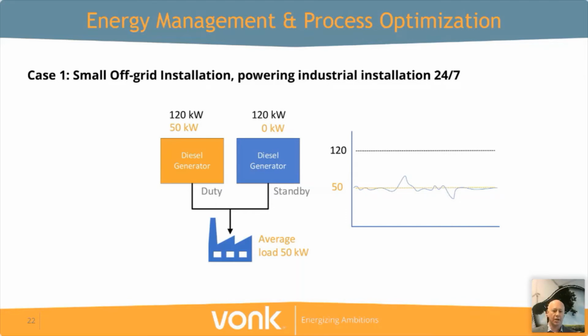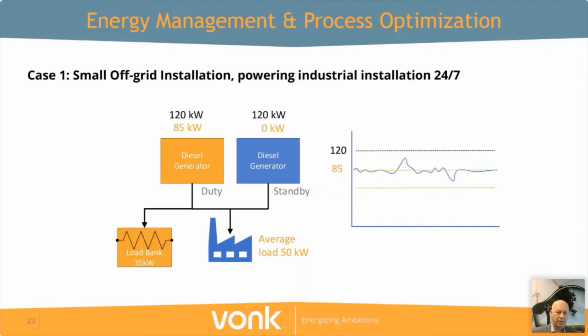So what is traditionally done is to put a load bank in place that's taking part of the energy, but that energy is actually being dumped. The diesel generator will be above the 70% load, so it will be in its sweet spot, but you lose quite a lot of energy in your load bank.